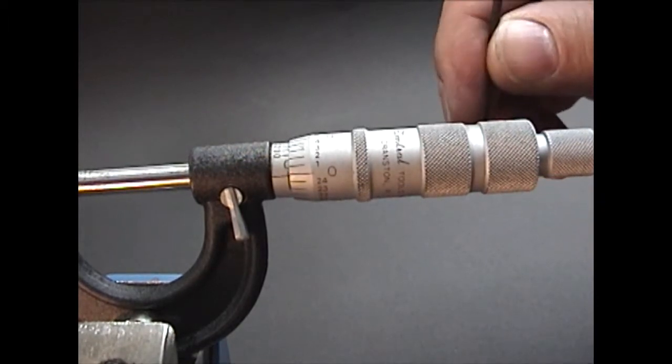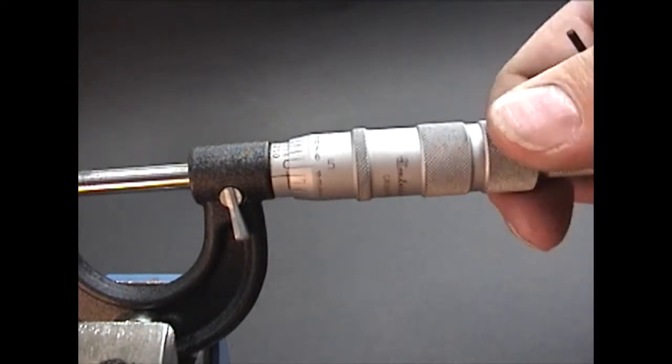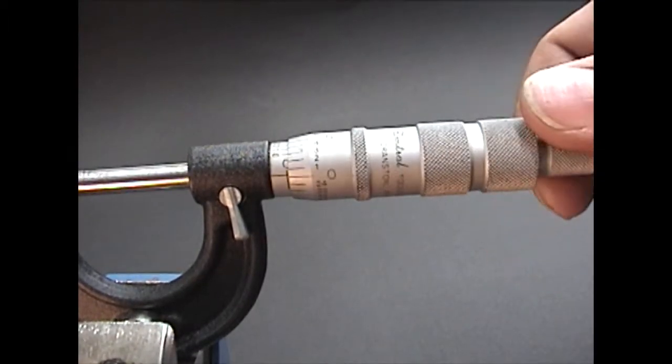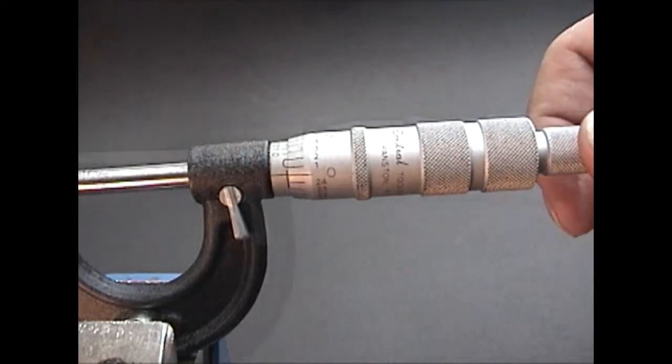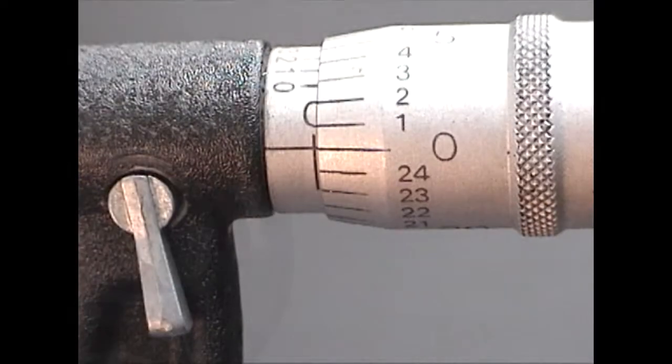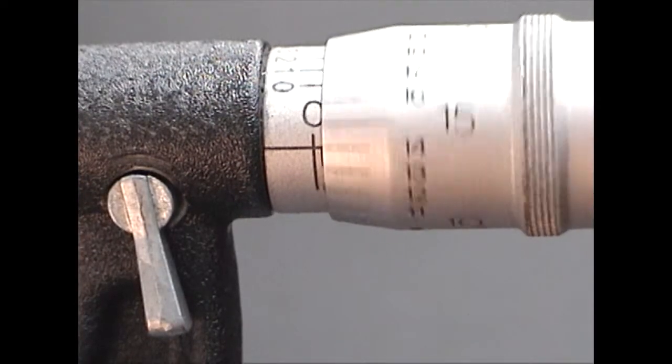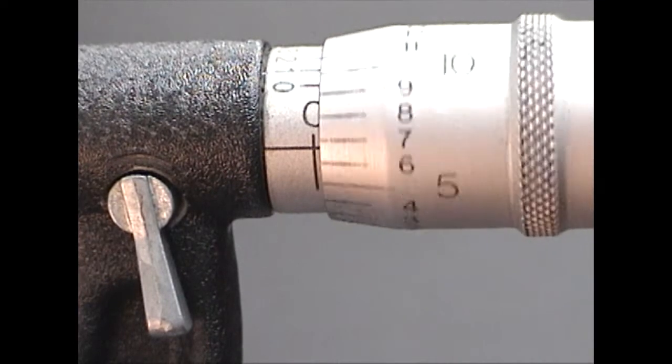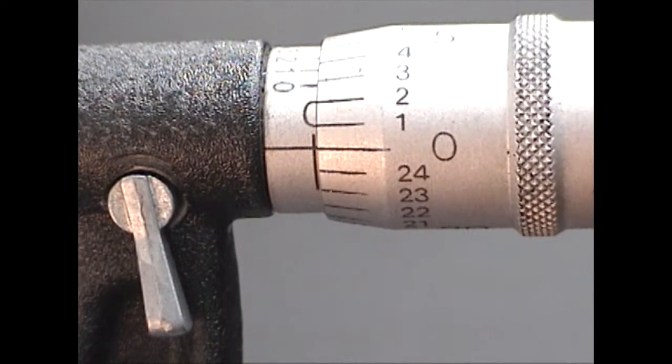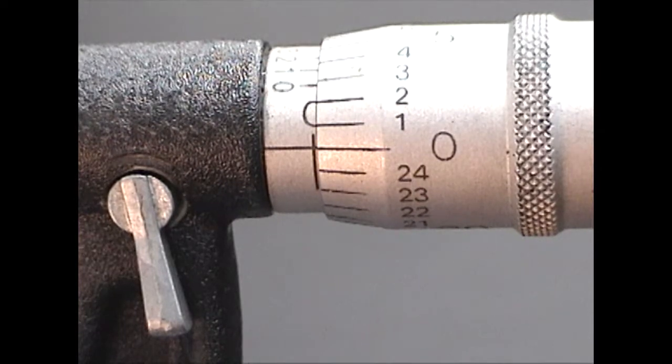Once the set screw is snug, tighten it some more so it won't come loose. Open and close the micrometer a couple of times to check the adjustment. Make sure the zero lines are properly lined up.